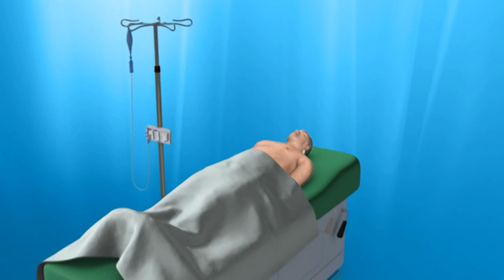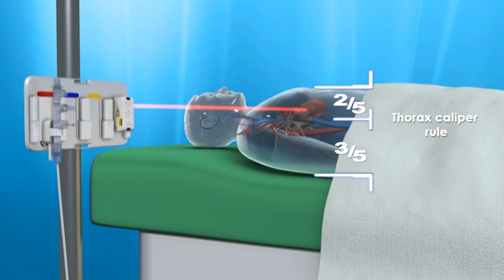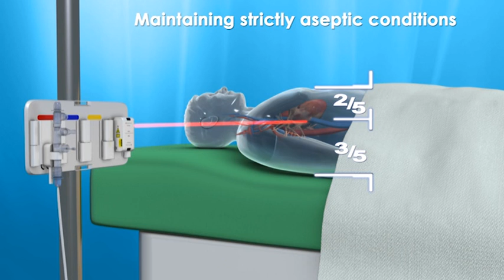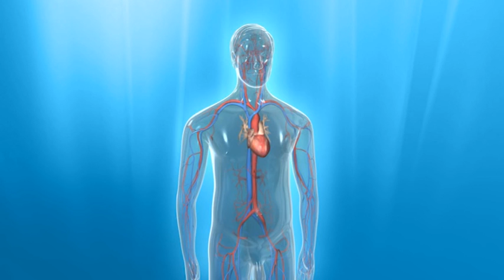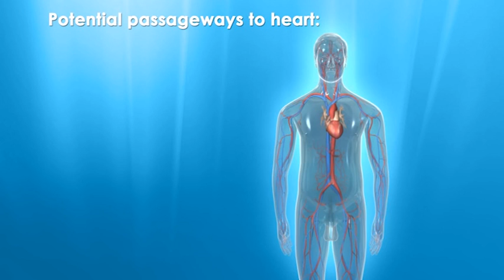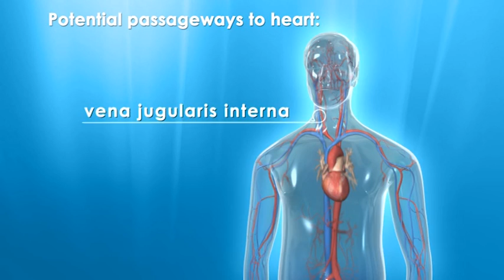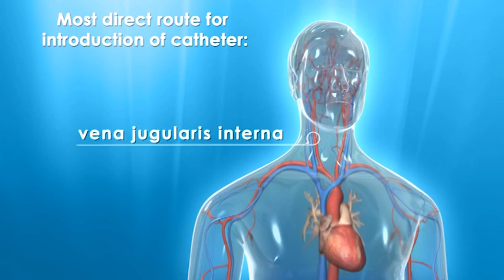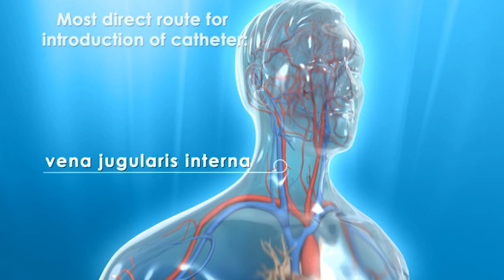With the patient in a supine position, the transducer must be placed at the height of the right atrium for zeroing. The zero reference point should be determined with care using a thorax caliper rule. Strictly aseptic conditions, in accordance with institutional policy, must be maintained at all times when handling the right heart catheter. Anatomically, there are several potential passageways to the heart for the RHC. It can be inserted into the vena subclavia, vena femoralis, vena mediana cubitis, or into the vena jugularis interna. Often, the right internal jugular vein, as the most direct route to the heart, is chosen for introduction of the catheter, also because of ease of identification and accessibility.